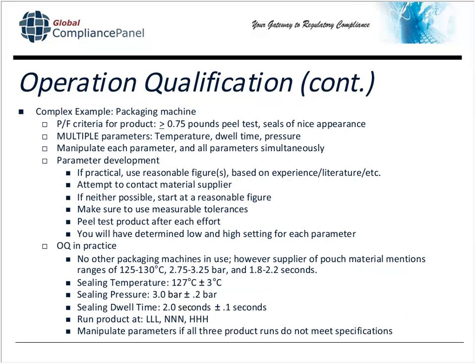Here's a more complex example. There's a packaging machine, which is different than a sealing machine, because while it still makes pouches, it does have multiple parameters. As I mentioned a moment ago, temperature, dwell time, and pressure are the 3 parameters. You're still going to manipulate each one, but you're going to manipulate all of them simultaneously. So as you can see, when you develop parameters, you develop them based on the piece of equipment you're using. Sealing machines and packaging machines are similar enough that the parameter development is identical. However, in practice, the OQ itself is a little different.